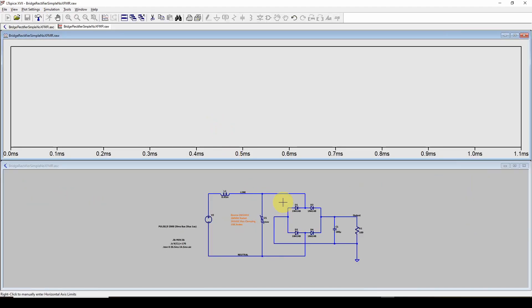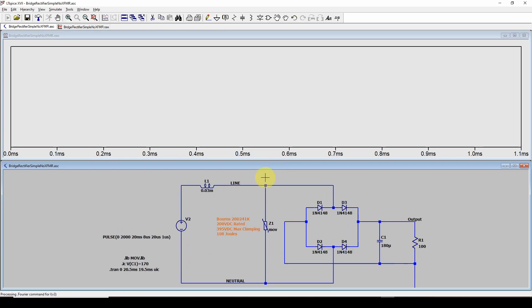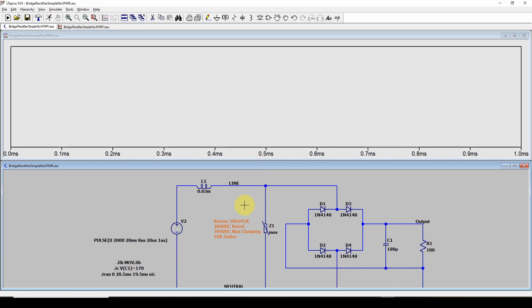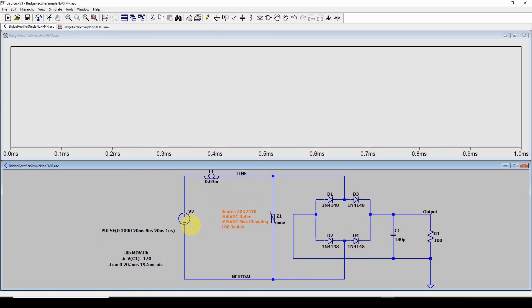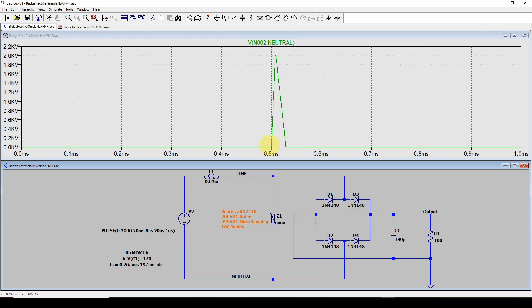So hit the running man and zoom in. The first thing I want to do is I want to measure the pulse. So again, I want to do a differential measurement, hover over this, click, click and drag. And then here is my incoming pulse. You can see peak of 2000 volts and it's there and gone in a half a millisecond, 0.6 milliseconds. So a fraction of a millisecond and it's gone.